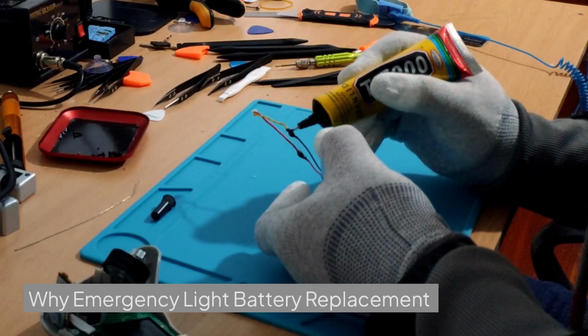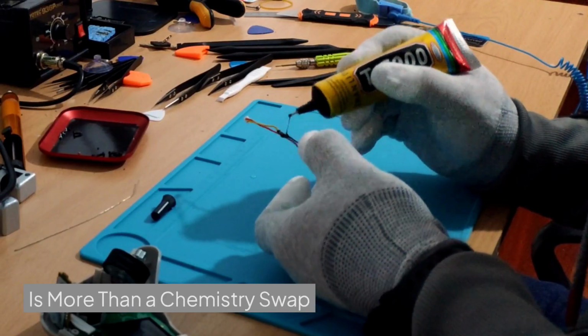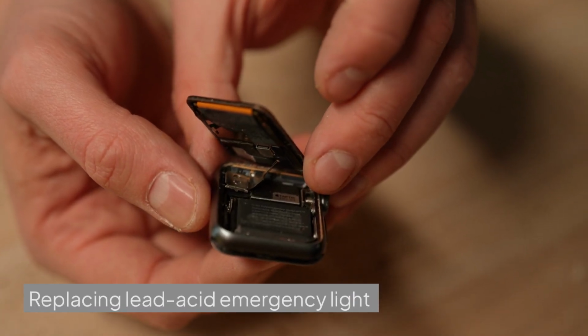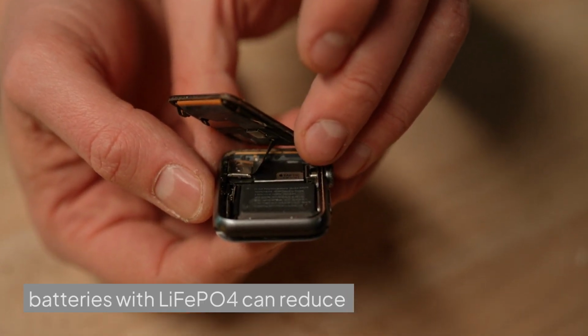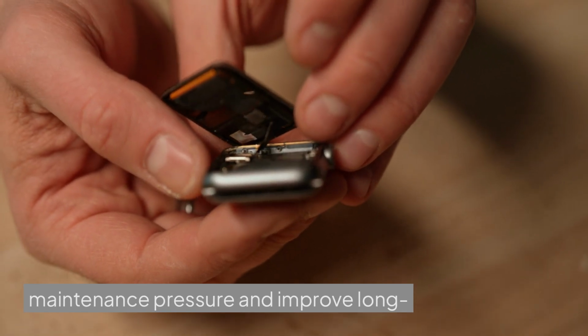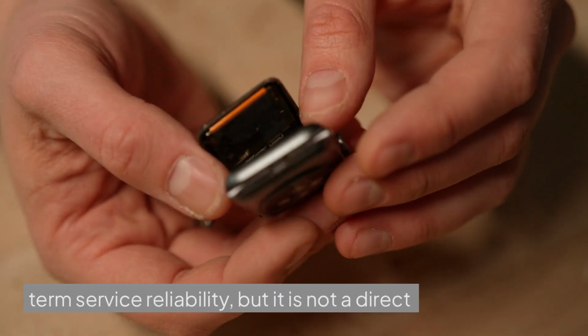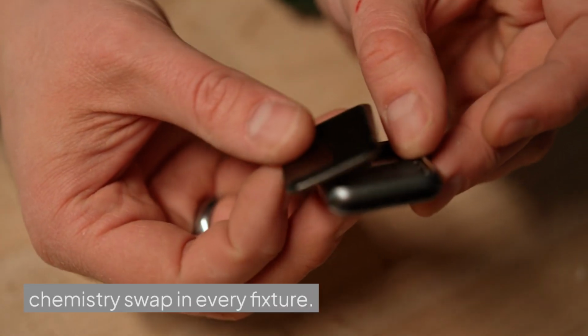Why emergency light battery replacement is more than a chemistry swap. Replacing lead-acid emergency light batteries with LiFePO4 can reduce maintenance pressure and improve long-term service reliability, but it is not a direct chemistry swap in every fixture.